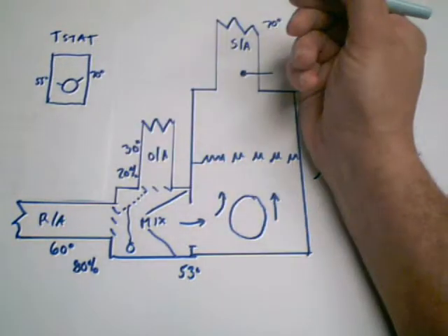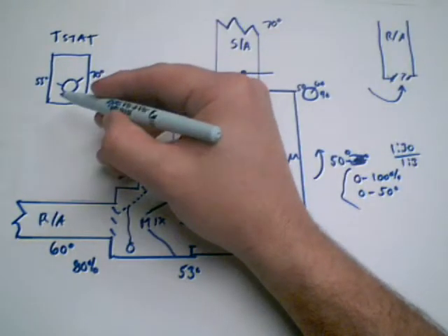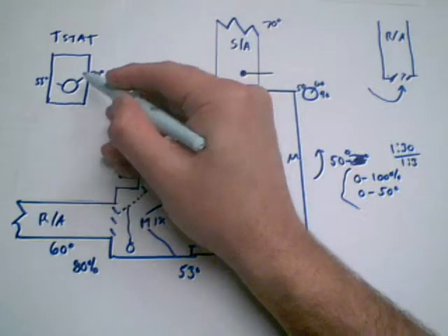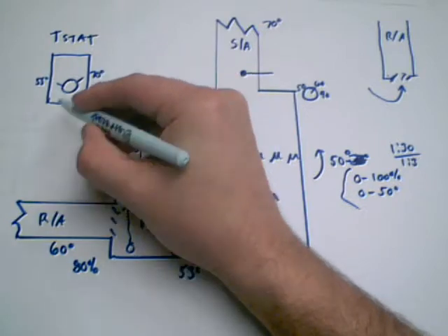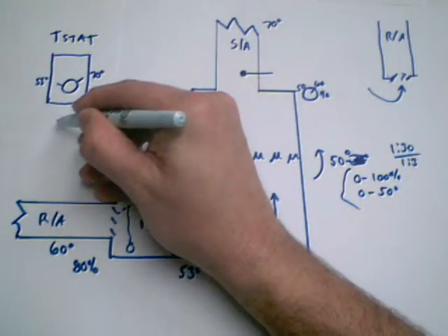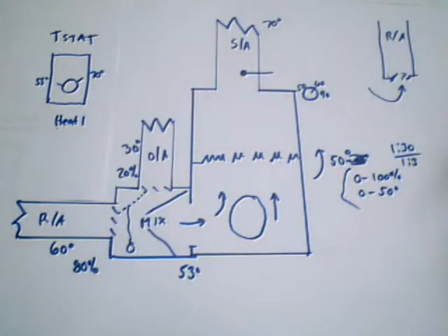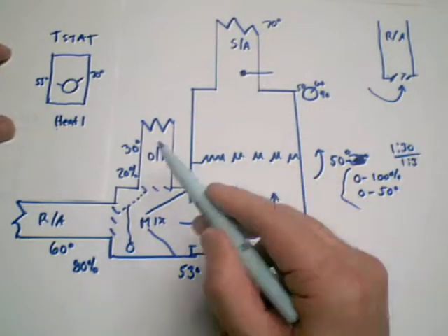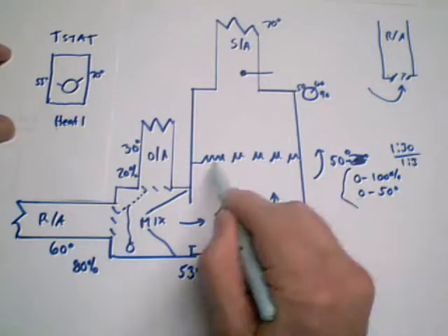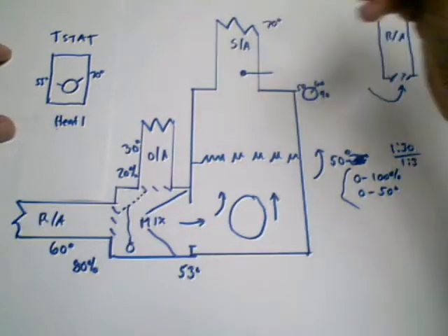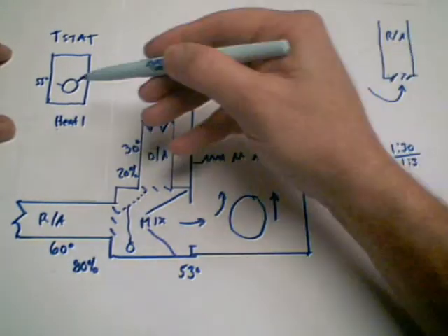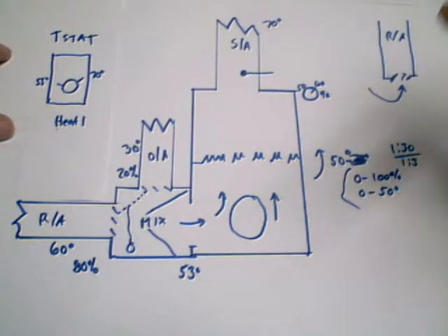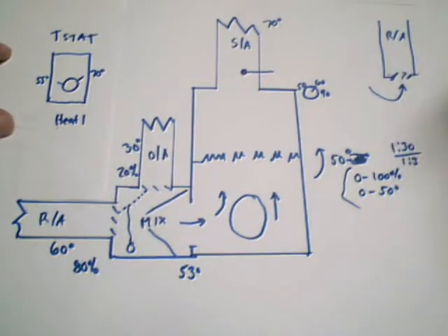It's just that simple from a user standpoint, but actually the thing sends out a couple of different signals. When you have a room temperature that falls below the set point by a degree, then it goes into first stage heat, which is just typically called heat 1. Heat 1 says, okay, we only need to raise it up a little tiny bit, so we don't necessarily need to have this flame on 100% and have this big influx of extremely hot air and then have it shut off all of a sudden. It would overshoot 70 degrees, and it would feel kind of like someone who regulates the heat in their car by turning it full on and then full off, full on, full off.